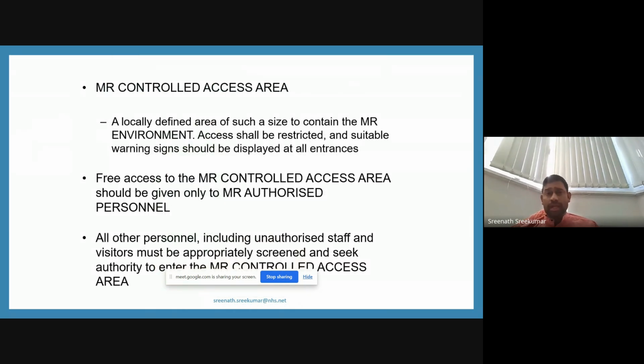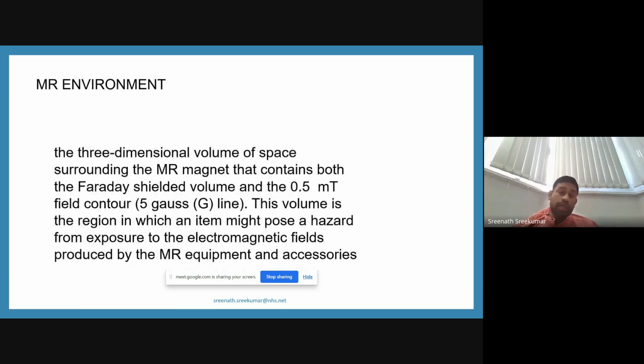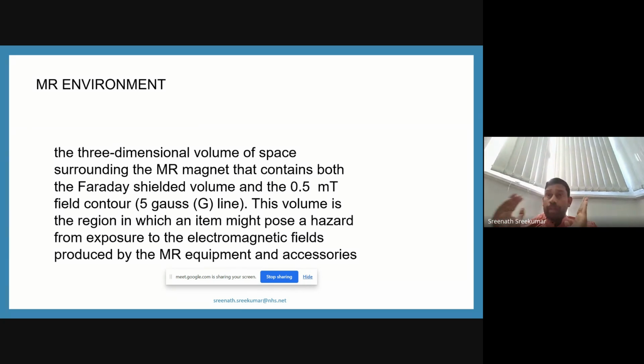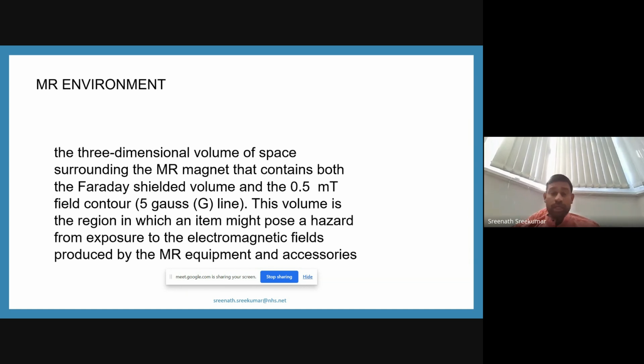Again, discussing the same thing: if somebody is going into the controlled access area, they should be monitored by a person with knowledge of MR safety, called an authorized person. Unauthorized staff should not enter without screening. The same applies to the MR environment, which is a Faraday shielded volume within the contour of the MRI environment, having a 0.5 millitesla or 5 Gauss line range. This volume might pose a hazard to active devices, and the electromagnetic field can alter the equipment and accessories.